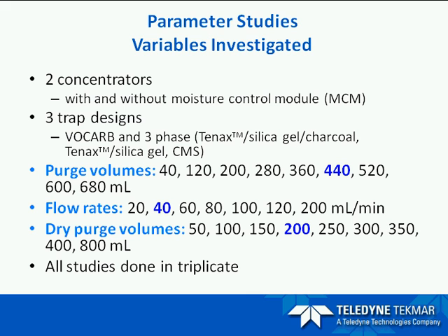Now, use of Tekmar's No. 9 trap, that's the new proprietary No. 9 trap we designed with the Stratum PTC, along with the redesign of the moisture control system of that instrument, help to provide the necessary means to effectively reduce this amount of water. Now, the standard parameters investigated are highlighted on your screen in blue, while the operating conditions evaluated are highlighted in black. Note, these conditions cover a wide range of values.